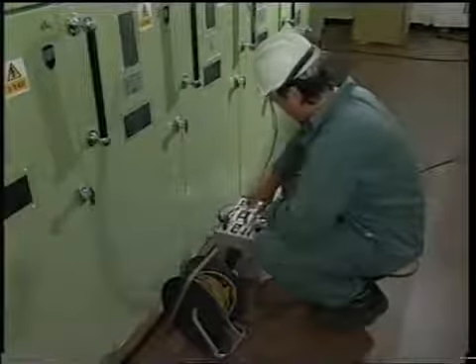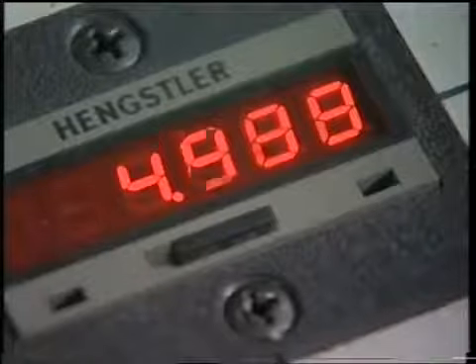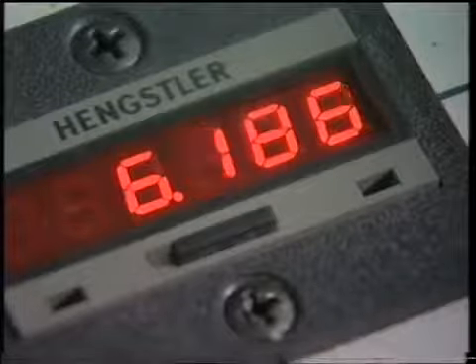Electrical circuit equipment requires special protection relays, which are usually fitted on the front panels of main and sub switchboards. Periodic maintenance testing of such relays is necessary to confirm their operation and accuracy. This work requires calibrated test equipment and is usually done by outside contractors during a major refit in dry dock. The equipment injects a set current and records the time for the relay to trip.